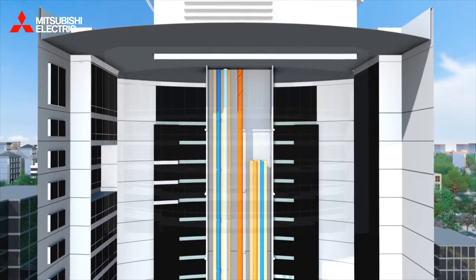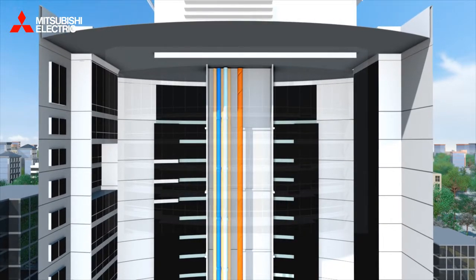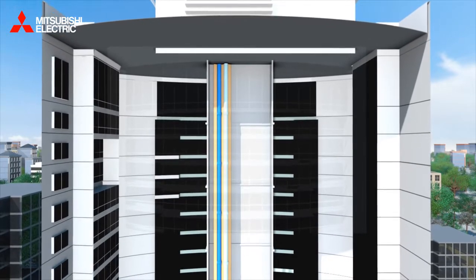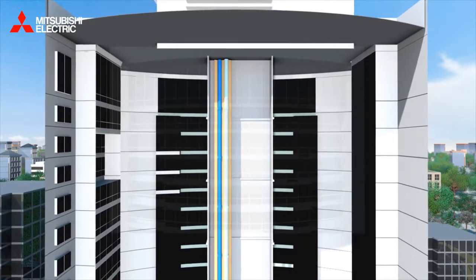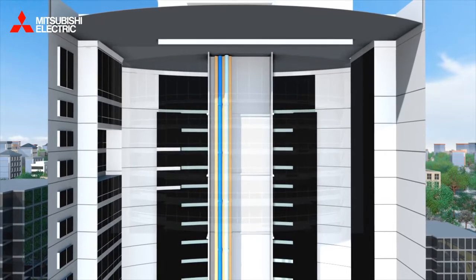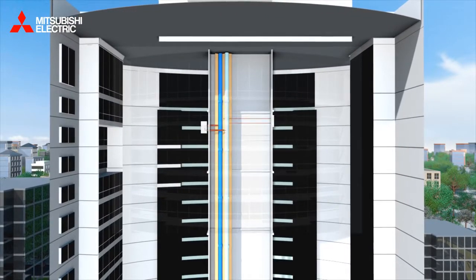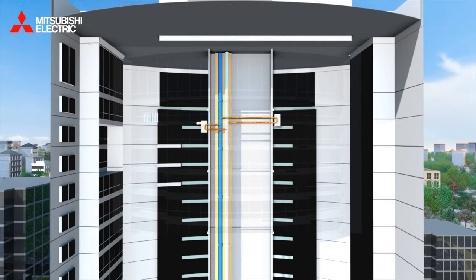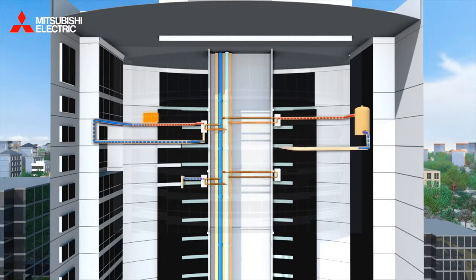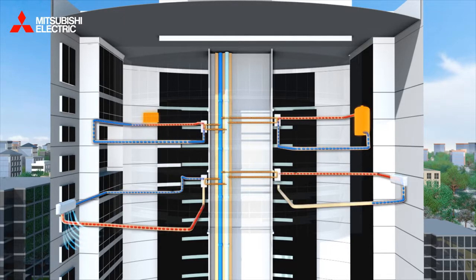With a single energy loop, we can remove the need for a high-temperature riser, remove the need for a boiler flue, and use a re-engineered chilled water riser to meet all of the heating, cooling, and hot water requirements using heat pump technology. Individual circuits can join to this energy loop to add or extract heat from it, giving us a more balanced use of technology throughout the building.